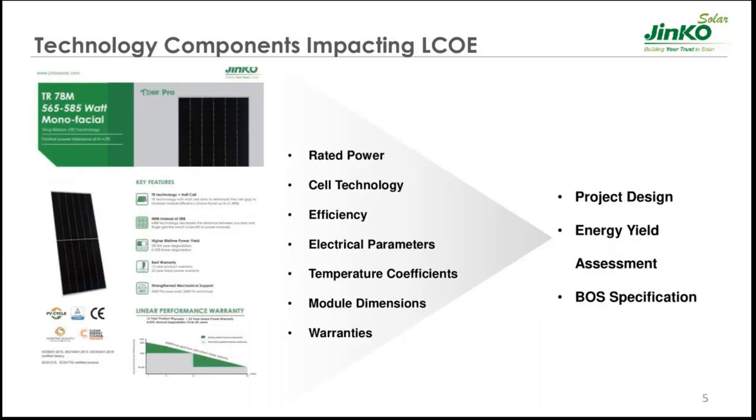So in terms of impacting the LCOE, we can, let's say, have two different aspects. One is the one driven by the rated power, the cell technology, the efficiency, and the electrical parameters. The first four parameters are going to change the project design, meaning they are going to change the BOS cost, the total cost of every component but the modules. This is very important because by increasing the power density, the efficiency of the module, we are going to reduce the land area, we are going to reduce the amount of mounting structure that we are going to install.